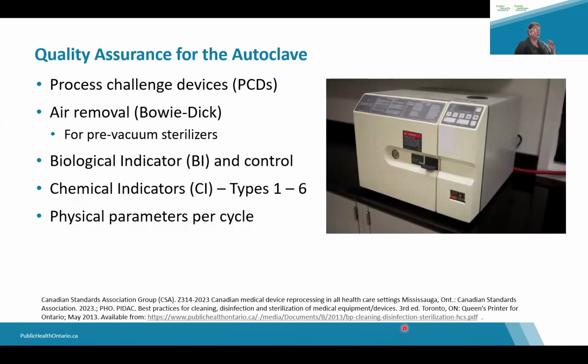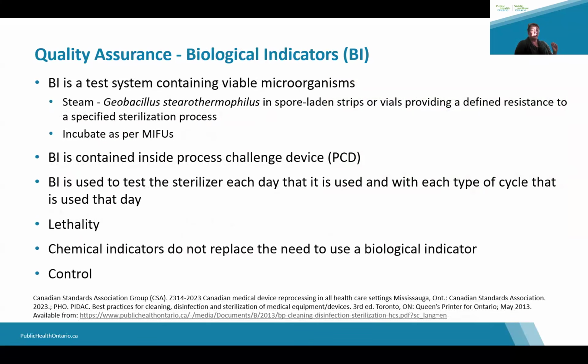So here is your autoclave, and now we're going to talk about quality assurance, about the process challenge devices, the purpose of the Bowie-Dick, which we actually did just cover a little bit, the biological indicators, chemical indicators, and physical parameters per cycle. Excuse me. So the manufacturer's instructions for use for the specific type of biological indicator that should be used in a particular sterilizer should be followed. So there are different instructions for that. And the purpose of the biological indicator is to assess the lethality of your sterilizer to make sure it has the ability to kill.